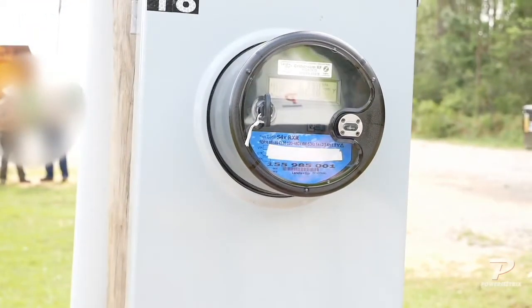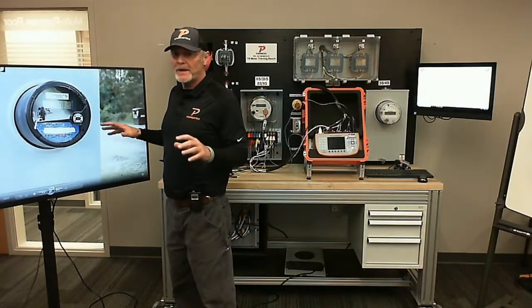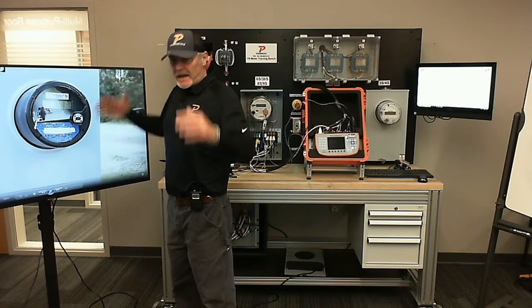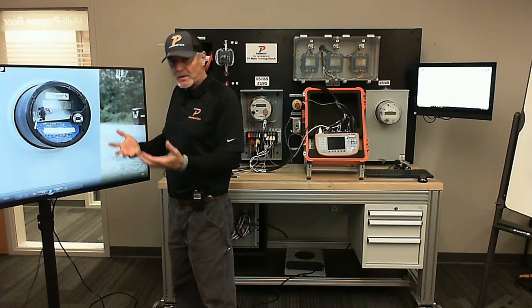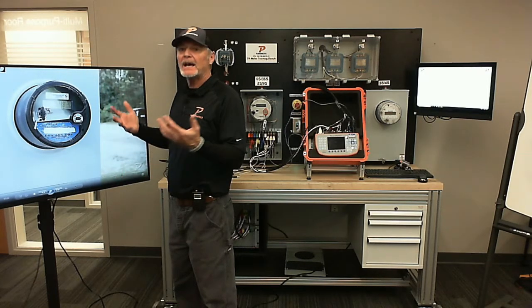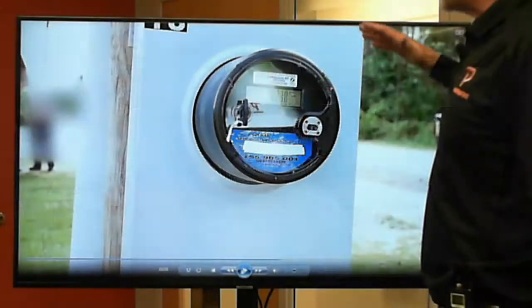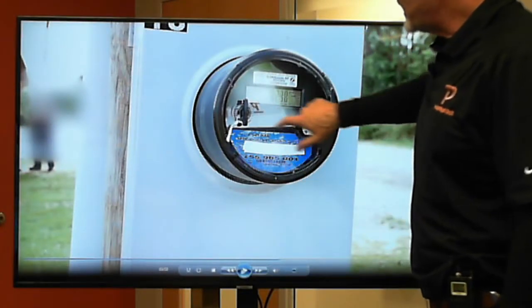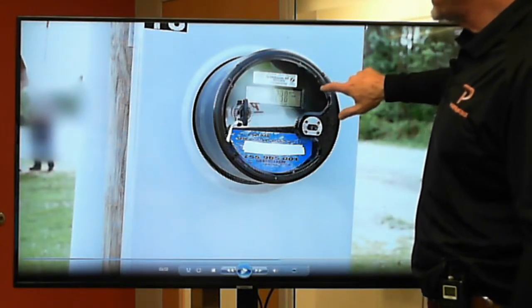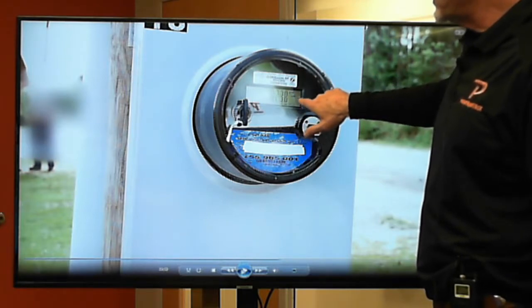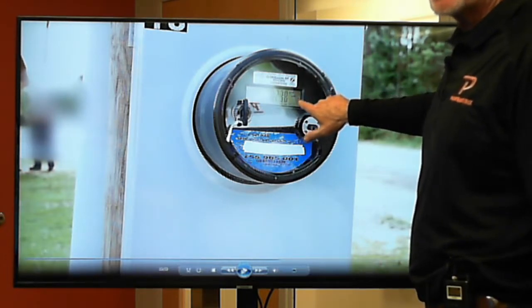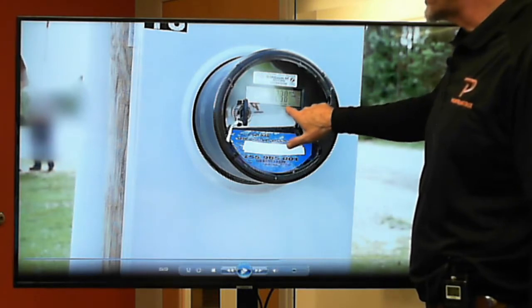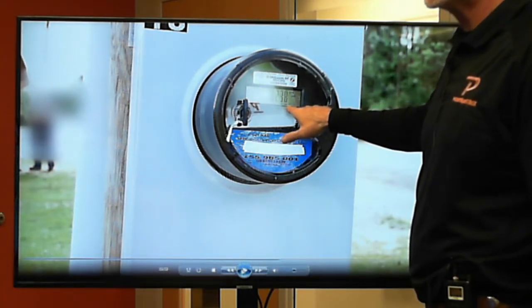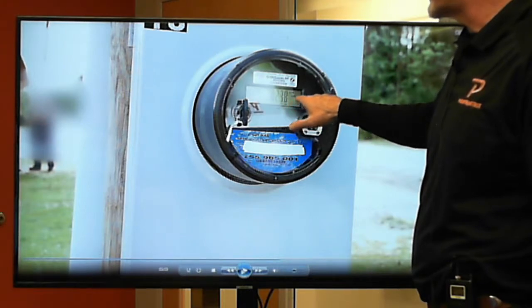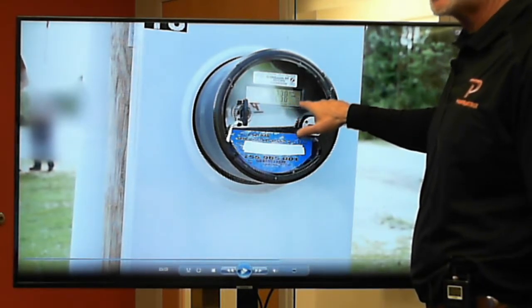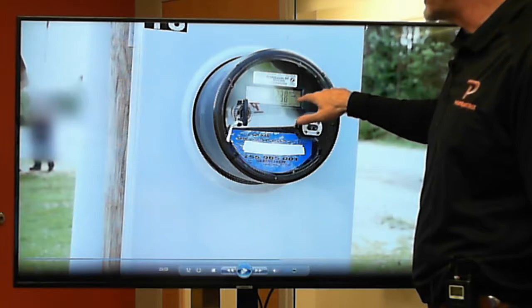Okay, so we've talked about this before, but when you go up there before you start testing, gather up your information and make sure that you're putting the correct service type in, what you're about to test, what you're dealing with, and you have information off the actual nameplate and face of that meter, and then also off the display screen, right? On the display screen, usually you're going to have either a Y or a delta for whether it's a Y or a delta service. You're also going to show that minimum voltage right there. So it's 277. If it's a Y, we're going to say it's a 277 480 volt Y is how we say the configuration is on that.